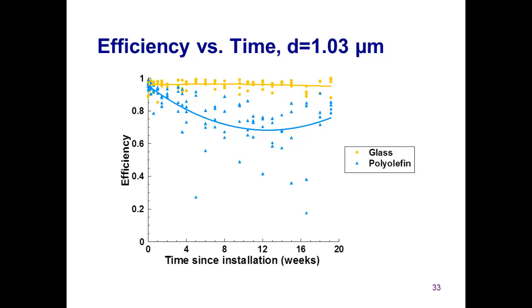We can see that over the entire test, the uncharged fiberglass filters did not show significant change in efficiency with time, while the synthetic media exhibited a decrease immediately after installation through about 3 months of use, and then increased, possibly as the filter began to clog with collected particles. It is important to note that this study was performed in Minneapolis in an urban environment. We would expect clogging to take longer than 3 to 4 months in a rural location.